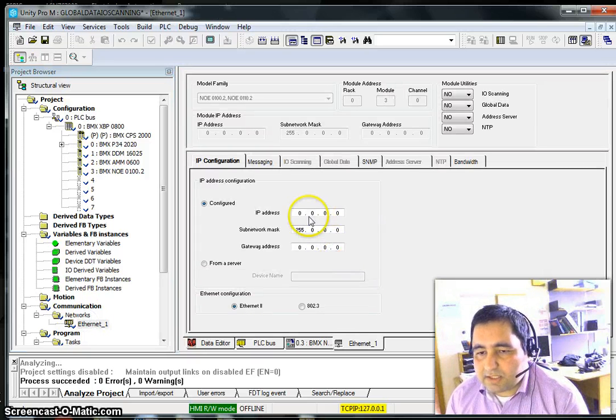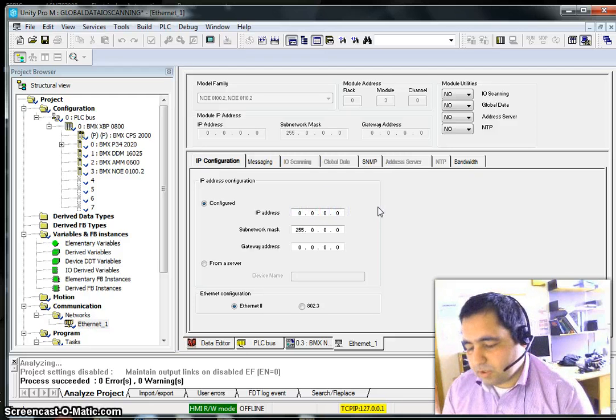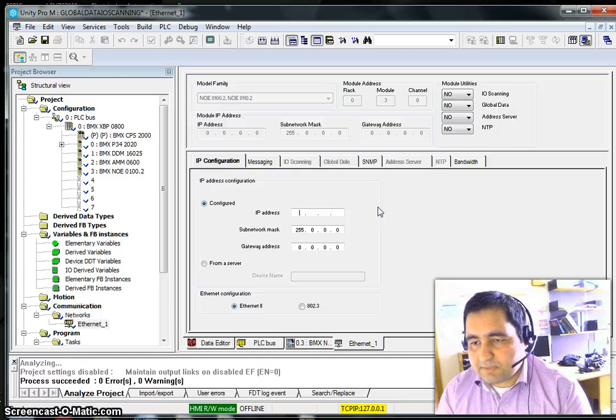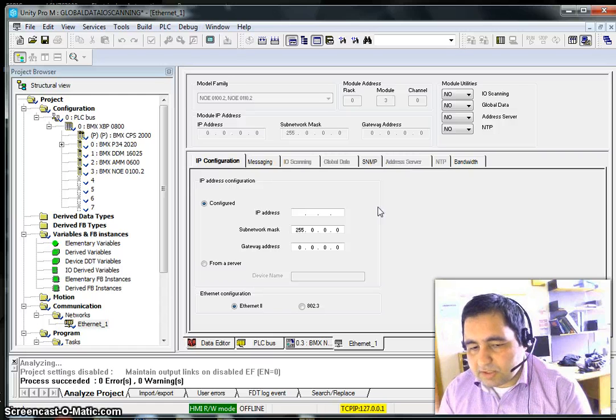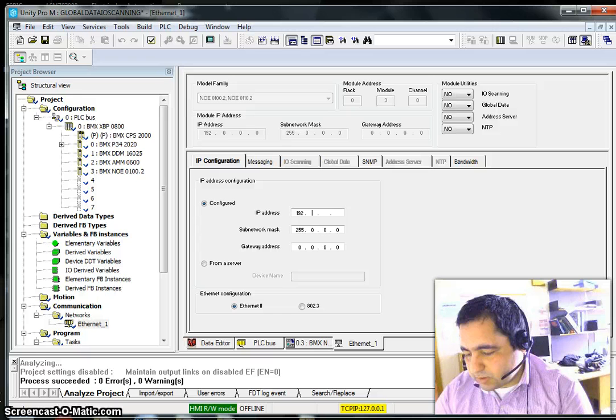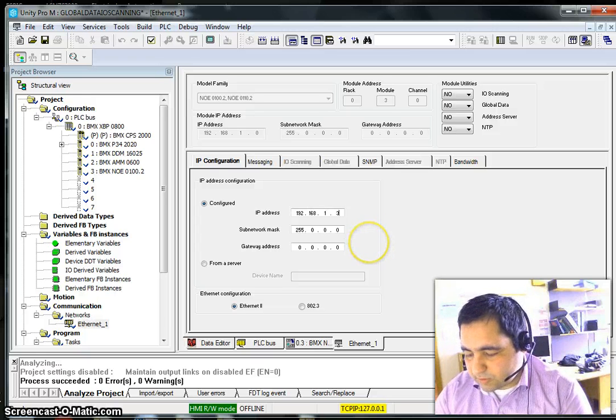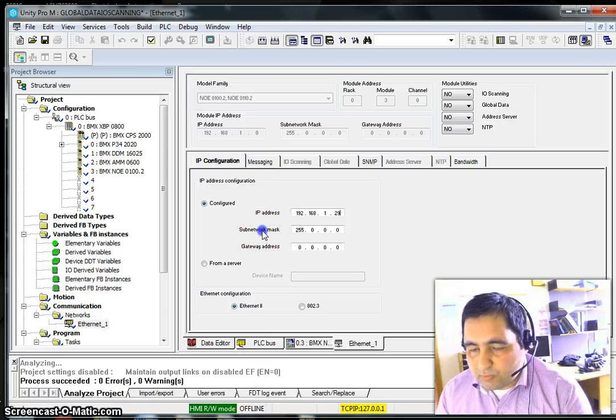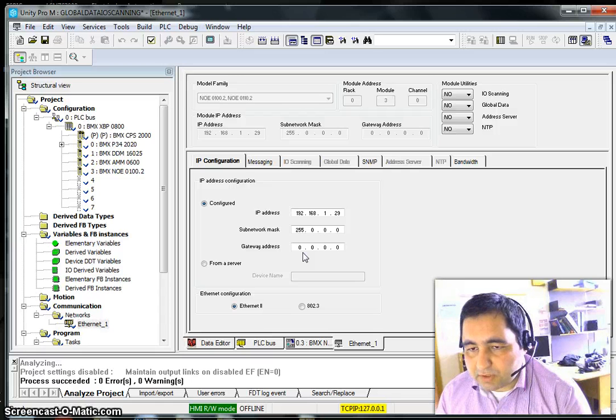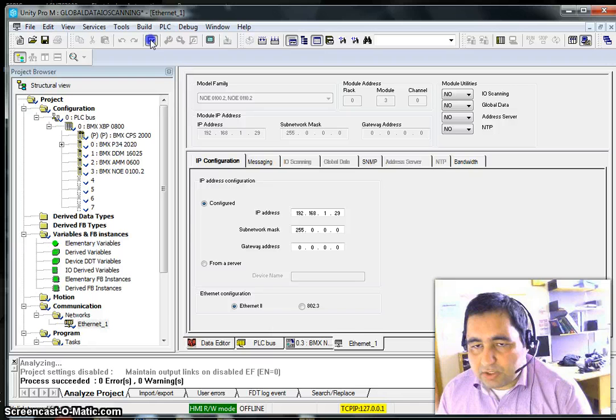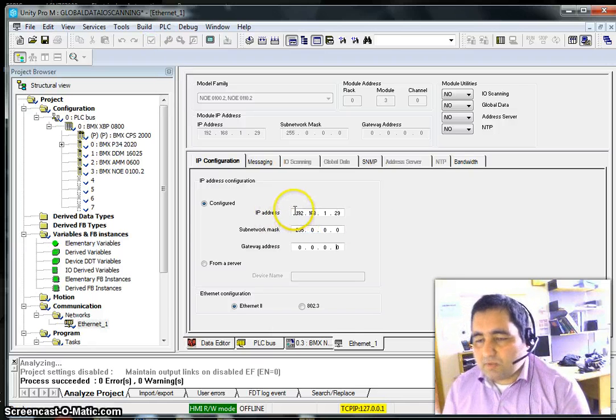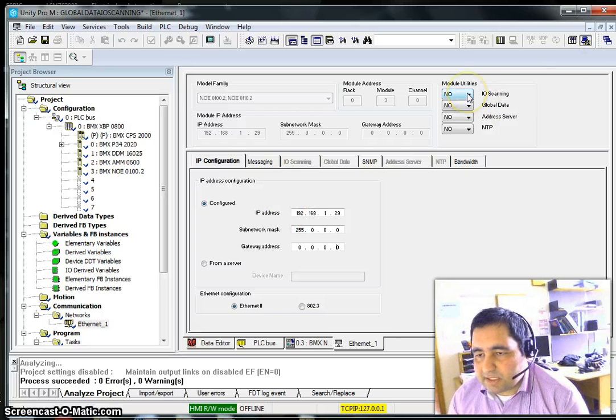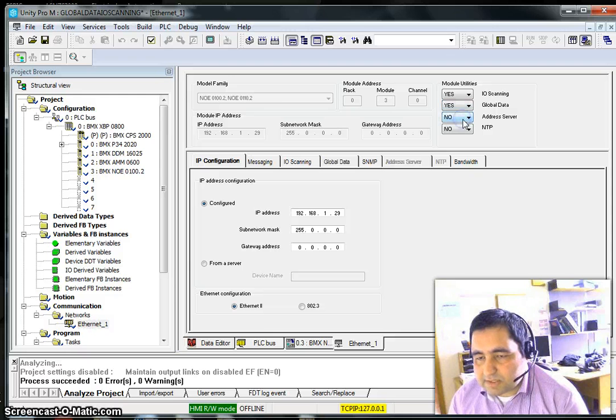Now our network is okay. We can click here and do the setup for our network. An IP address is required, so let me set it — the IP address for my PLC is 192.168.1.29. I'll leave the subnet and gateway as they are. Since I want to use two services — IO Scanning and Global Data — I need to change the setting from 'No' to 'Yes'.